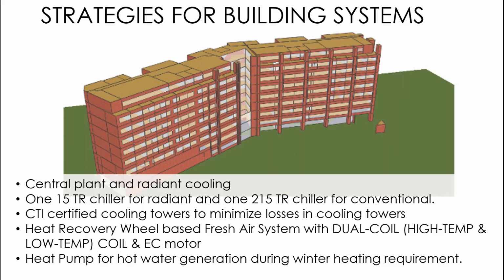So by virtue of this delta T and the higher temperature range, radiant chillers typically work at around 0.45 kilowatt per ton, and a conventional chiller at about 0.67 kilowatt per ton. So that is almost about 33% saving just by virtue of operating at a higher set point. And then when we talk about hot water generation, which is also required during a couple of months in winters, and this being a minister's building, the ministers and the IAS officers have this habit of even working late in the night, and therefore they would require winter heating.